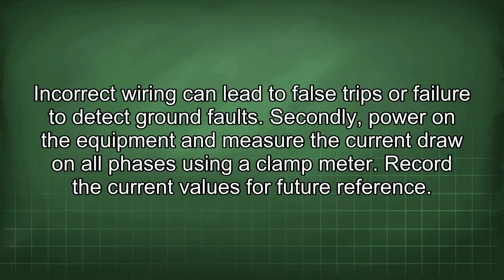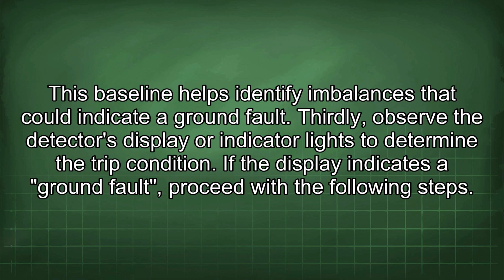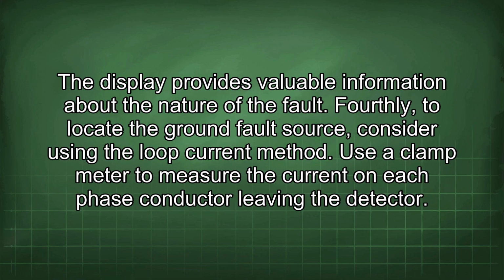Secondly, power on the equipment and measure the current draw on all phases using a clamp meter. Record the current values for future reference. This baseline helps identify imbalances that could indicate a ground fault. Thirdly, observe the detector's display or indicator lights to determine the trip condition. If the display indicates a ground fault, proceed with the following steps. The display provides valuable information about the nature of the fault.